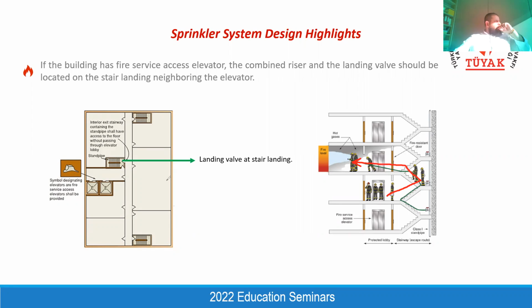That's why it's important to have the landing valve system just next to the fire escape stair, neighboring the fire service access elevators, because the fire brigades are coming with these elevators. They are preparing within the fire protection lobby, and then they enter the fire escape stairs to go to the upper floors, and they are using the landing valve and the riser located within the fire escape stair. It means if you have two separate staircases, the landing valve is recommended to be provided within the staircase neighboring the fire service access elevator. It's really important for us. Otherwise, they need to change location.